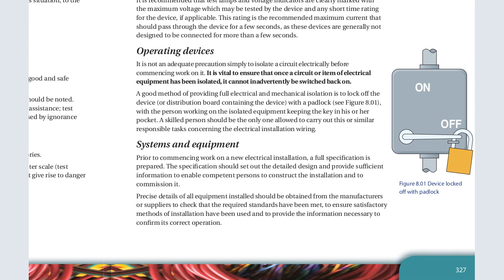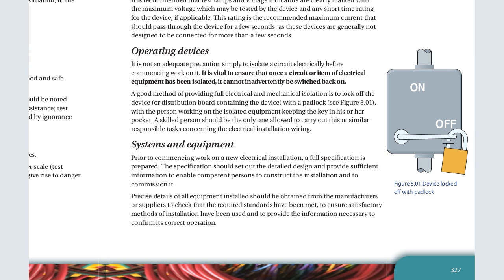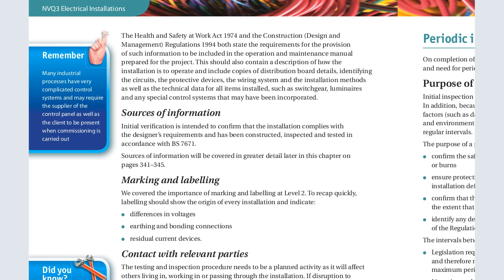So the system and equipment. What happens to the system and equipment? Now, prior to commencing the work on an electrical installation, a full specification is prepared. That is, the specification should be set out on a detailed design and provide sufficient information to enable competent persons to construct the installation and to commission it. So the precise details of all equipment installed should be obtained from the manufacturers or suppliers to check that the required standards have been met, to ensure satisfactory methods of installation have been used, and to provide the information necessary to confirm the correct operation.